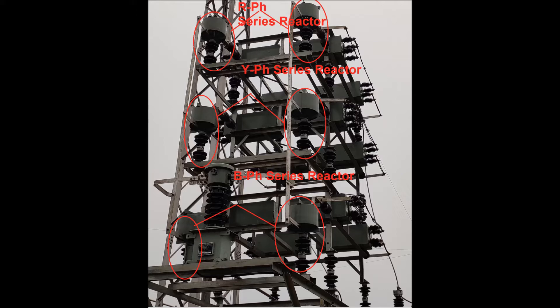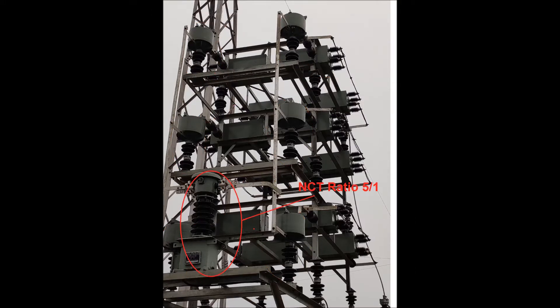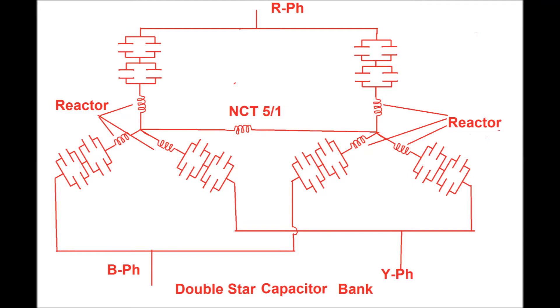In this diagram, the series reactor in each phase and each star has been shown. Since it is double star connected, the number of series reactors is six. The NCT (Neutral CT) has also been shown. The ratio of the NCT here is 5/1, although it may be 2/1 or 3/1. The equivalent circuit of the double star capacitor bank is shown, with the NCT connected between the star points.